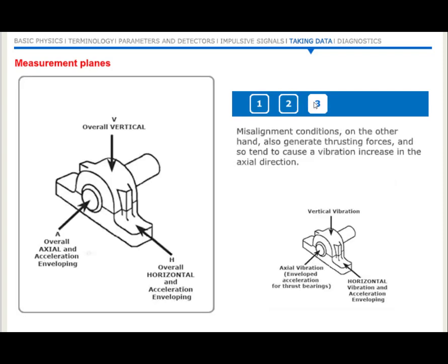Misalignment conditions, on the other hand, also generate thrusting forces, and so tend to cause a vibration increase in an axial direction. When you take axial measurements, be sure that the instrument's tip is held firmly against a suitable surface, such as the bearing housing or some other machine face. Where a machine employs thrust bearings, these are taking load in the axial direction, and therefore measurements of enveloped acceleration should also be taken in the axial plane.